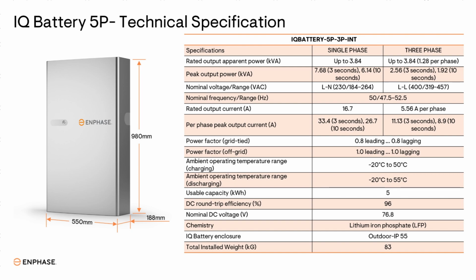Talking about the 5P technical specifications. The same battery you can use with either single phase or three phase. We also had a product like single phase batteries earlier, so it is quite similar to that one. The continuous output power from these batteries is, in single phase, up to 3.84 kVA of output power. And if you are using the batteries in three phase, you are going to get output power of 1.28 per phase.